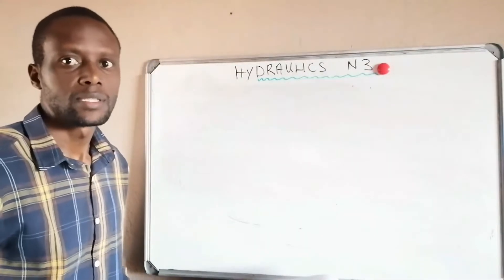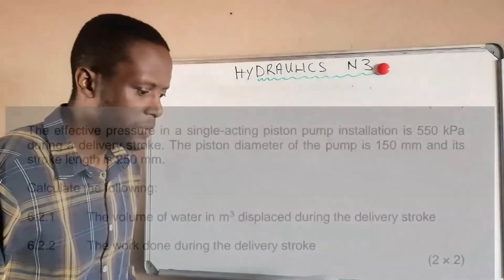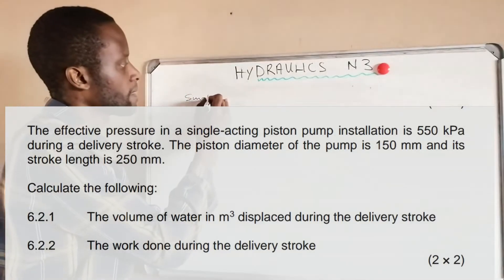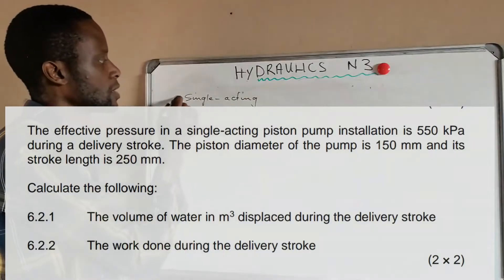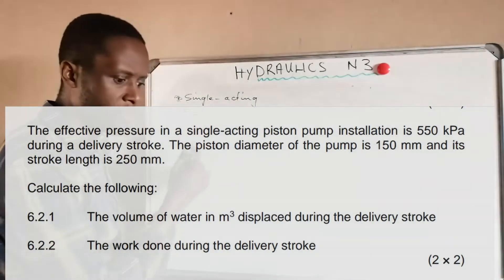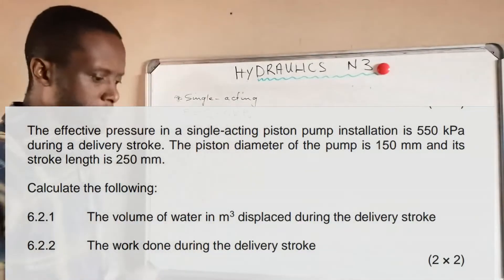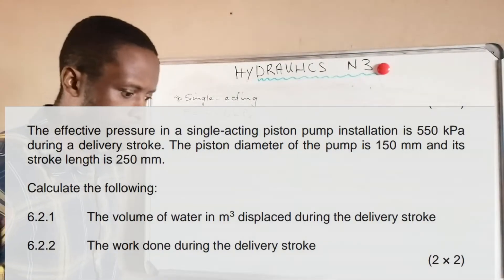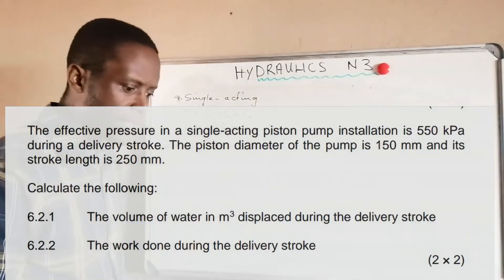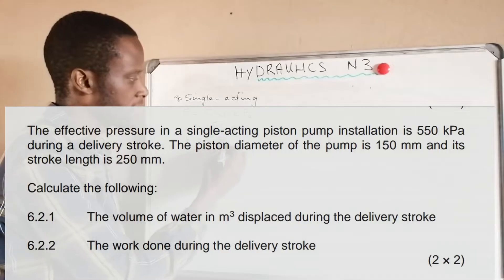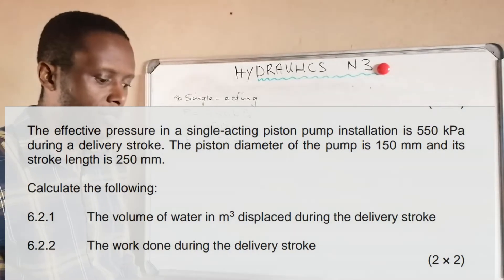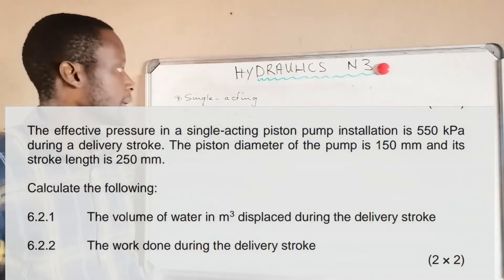Here is a practice question. The effective pressure in a single acting piston pump installation is 550 kilopascal during a delivery stroke. The piston diameter is 150 millimeters and the stroke length is 250 millimeters. Calculate: (a) the volume of water in cubic meters displaced during the delivery stroke, and (b) the work done during the delivery stroke.